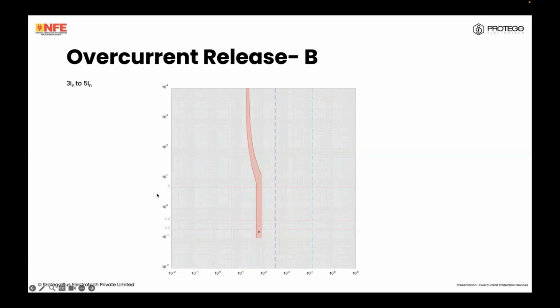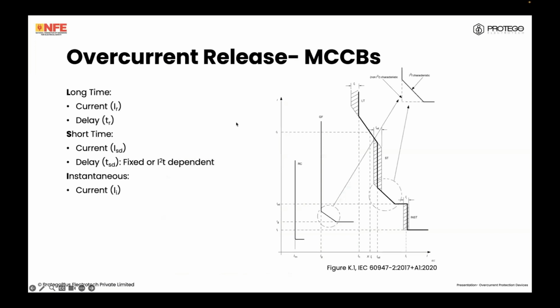So the current required to cause disconnection for 5-second disconnection, for 0.4-second disconnection, and for 0.2-second disconnection is the same. Same thing for C curve MCBs. But for D curve MCBs, 0.4 and 0.2 will have one value. However, 5 seconds will have a different value. So this will change the earth fault loop impedance. We'll get into that a little later. For K, same story. For Z, it is again the same value. These are again manufacturer defined, so it may differ per manufacturer.